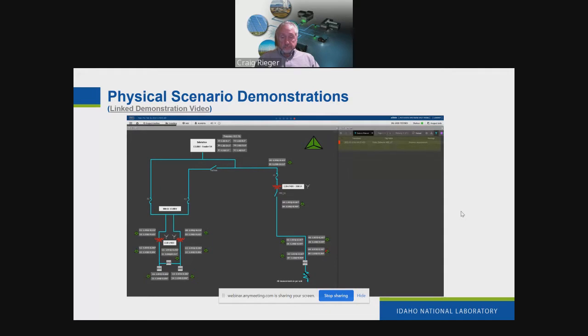This distributed state estimator is not intended to replace the state estimator in the EMS system at the control center. This is an independent system to detect and locate anomalies due to cyber attacks or to misset equipment or malfunctioning sensors. It can also be used to provide an independent verification for the state estimator on the energy management system.